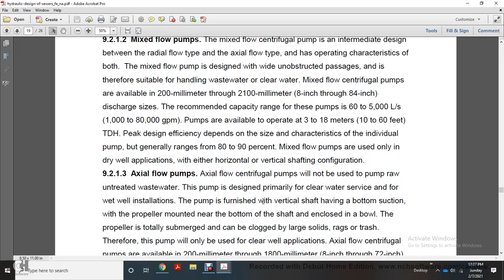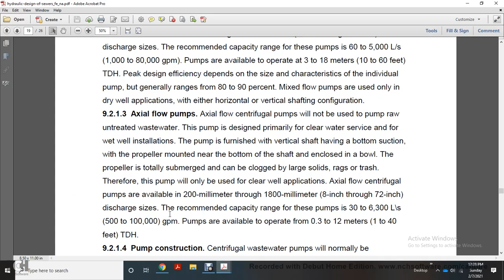Alright, axial flow pumps. Axial flow centrifugal pumps will not be used for pumping raw, untreated waste. The design is primarily for clear water services for the wet well installation. Pump is furnished with a vertical shaft with the bottom suction, with the propeller mounted near the bottom of the shaft, enclosed in a bowl. Propeller totally submerged and can be clogged by large solids, rags and trash. Therefore, pump will only be used for clear water application. The axial flow centrifugal pumps are available in 8 inches to 72 inches discharge size. Recommended capacity ranges between 500 to 100,000 gallons per minute. Pumps are available in the range of 1 to 40 feet total dynamic head.